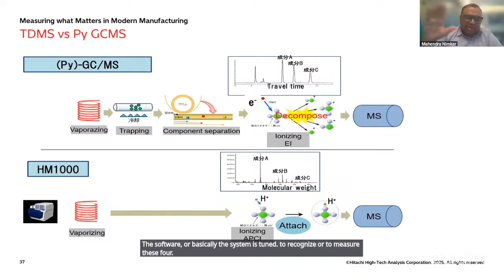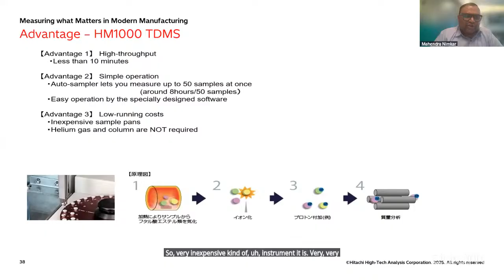It comes with the auto sampler, so you can do 50 samples at a time. It is a very high throughput system with low running cost, because we are not using any helium gas, any columns, or solvents, so you don't need a wet lab for this. It is a very inexpensive instrument, with very low running cost, I would say.